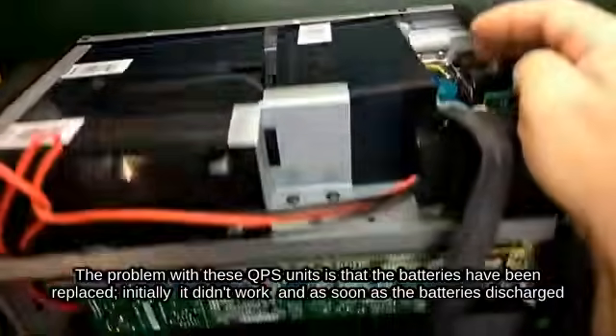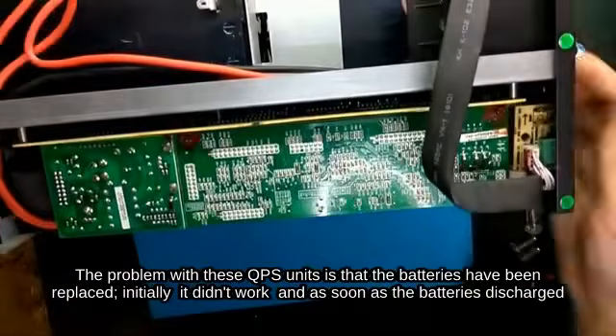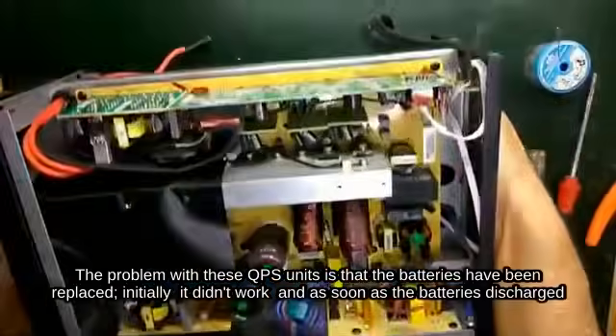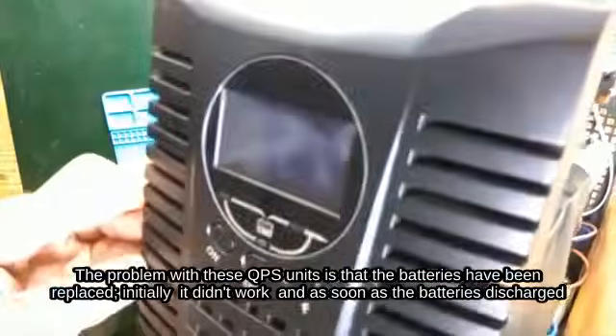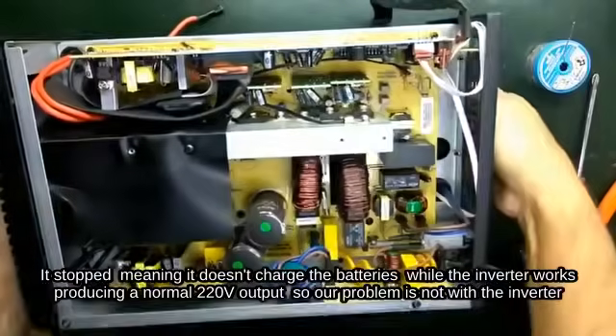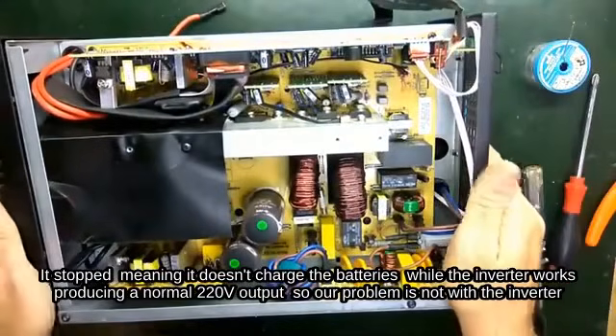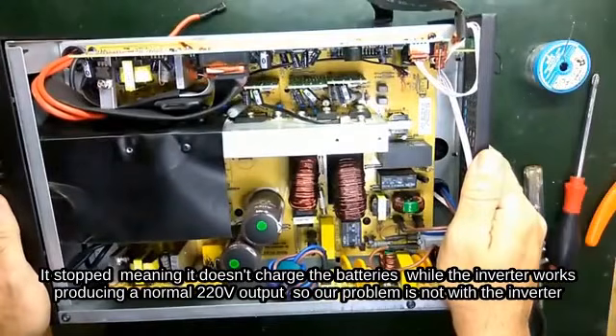The problem with this UPS is that the batteries have been replaced. Initially it didn't work, and as soon as the batteries discharged, it stopped - meaning it doesn't charge the batteries - while the inverter works, producing a normal 220V output. So our problem is not with the inverter.